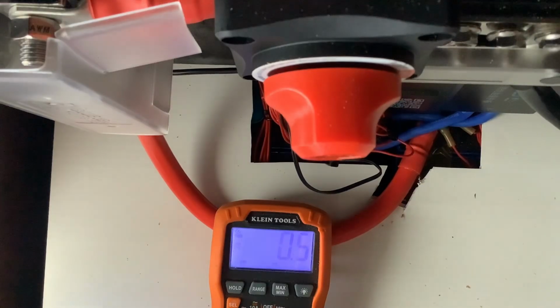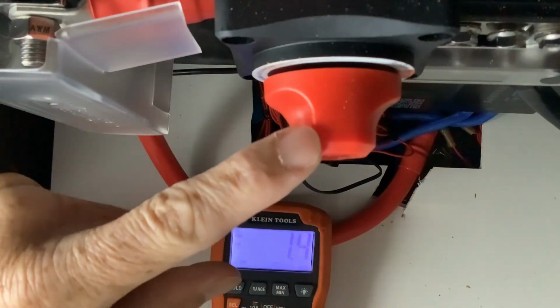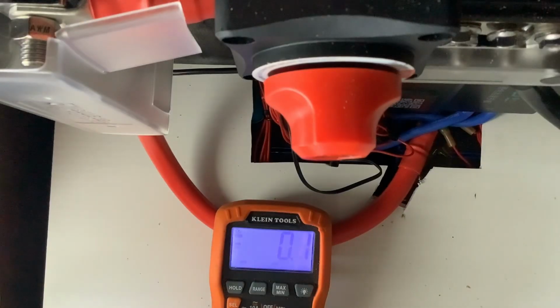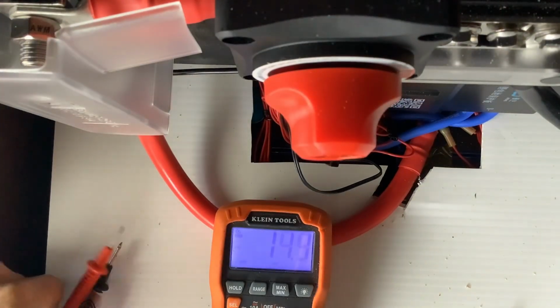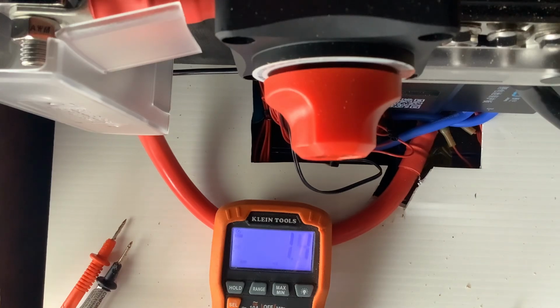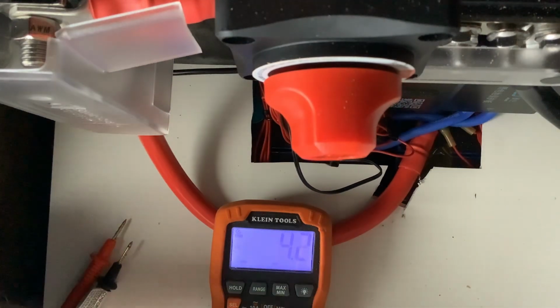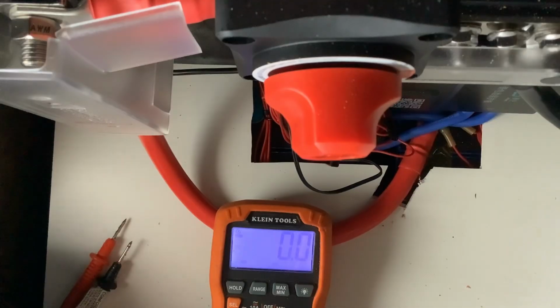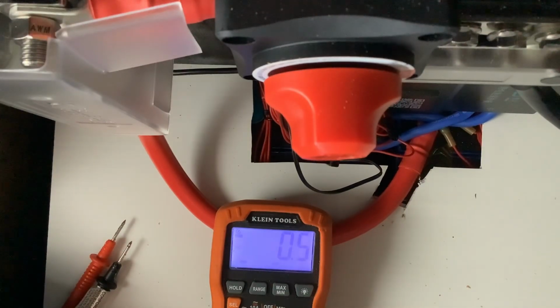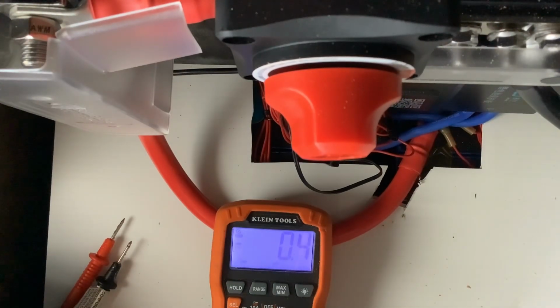Here I have the shutoff for the other bank, the rest of the battery bank, and I've got this turned down to 10 amps right now coming in from the charger. I'm going to take care of setting the voltage here first. But before that, I'm going to disconnect all the other batteries and let it just sit. I'll turn down the charging voltage so that when I shut this off, I'm not shutting off a whole bunch of current flowing through. I know it's only 10 amps, but when it's not necessary, it's not necessary.